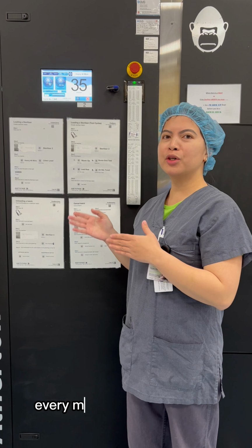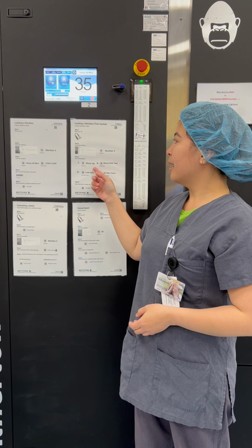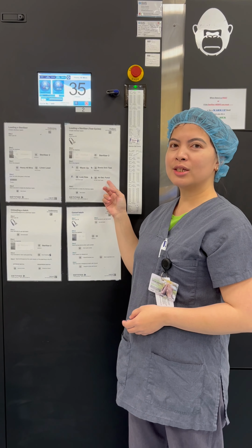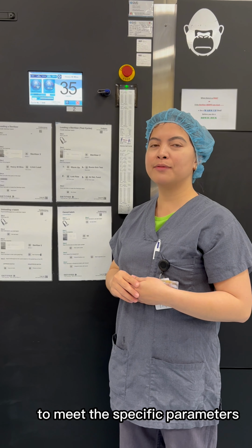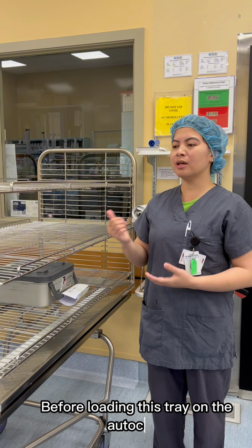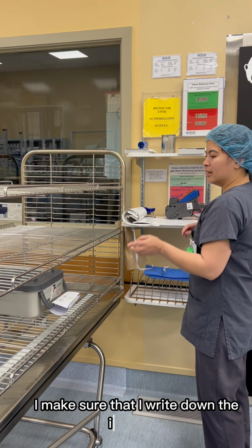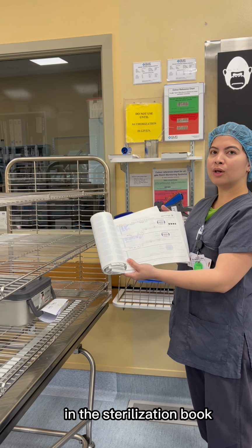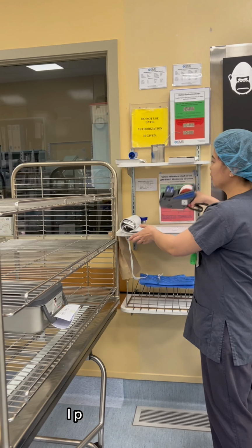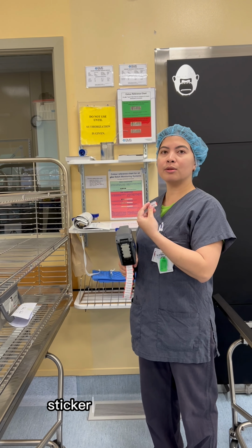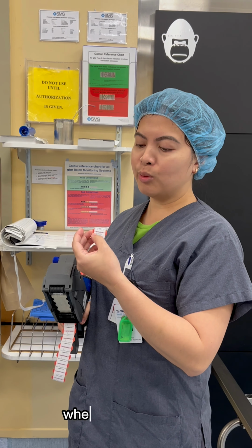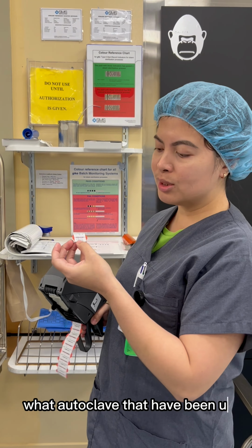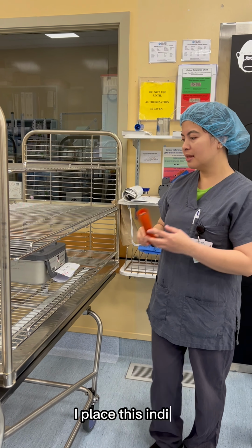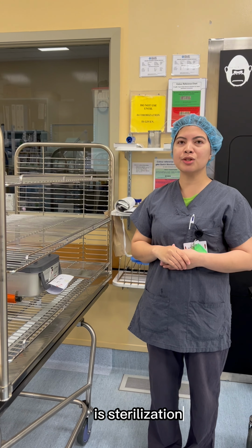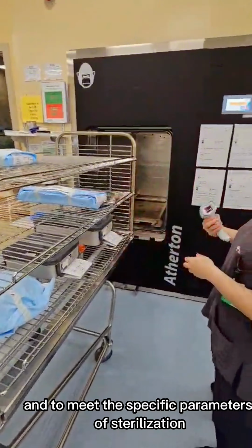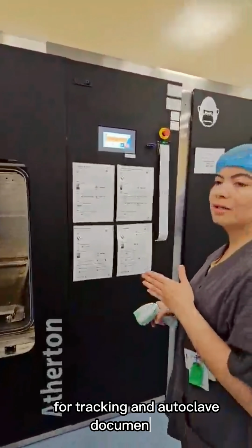So this is our autoclave. Every morning we do monitoring and testing: warm up, leak test, Bowie-Dick test, and air detection function to meet the specific parameters for effective sterilization. Before loading this tray on the autoclave, I make sure that I write down the item here in the sterilization book for autoclave documentation. I put a sticker, and this sticker will tell you the cycle information, the date when this is sterilized, what autoclave has been used, and the cycle number. I place this indicator to measure the effectiveness of sterilization and to meet the specific parameters of sterilization. Scanning them again for tracking and autoclave documentation.